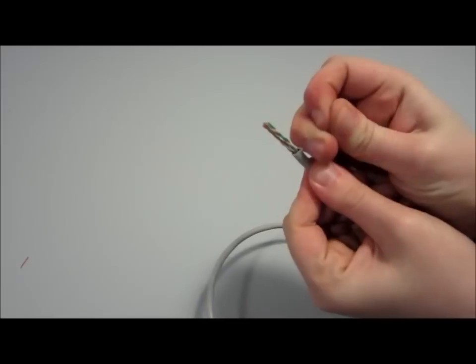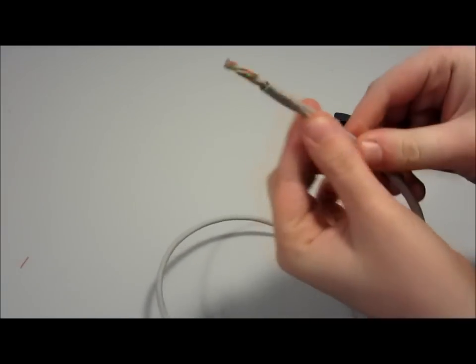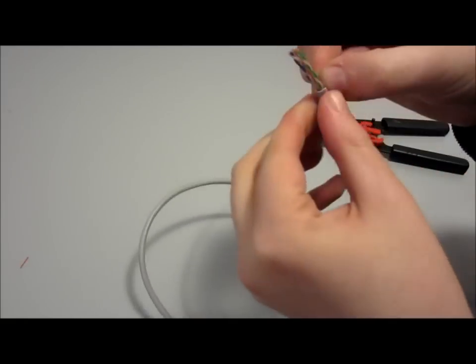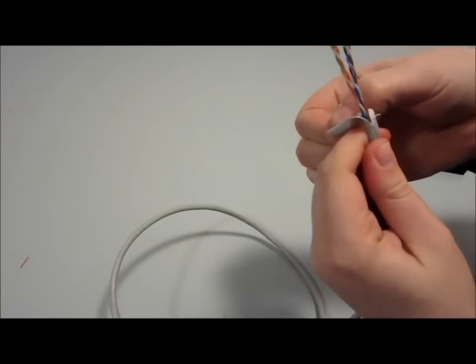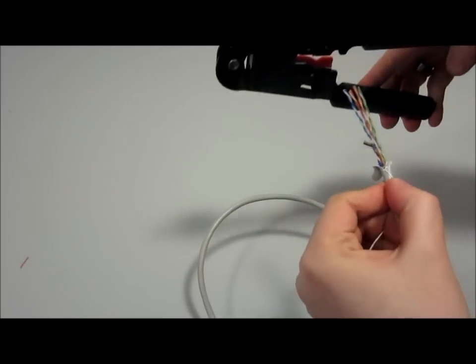Use the string to pull down on the PVC outer layer. Any excess, including the internal cores, should be trimmed up to the point where you first stripped the outer PVC layer. We trimmed down the internal cores to this point as they may have been damaged once removing the outer PVC layer.